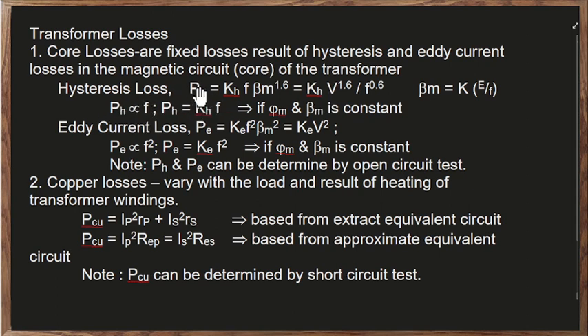P sub H stands for hysteresis power loss. We have our constant K sub H, frequency times the flux, the flux raised to the power of 1.6, no? If the given is voltage, then you have V to the 1.6 over the frequency to the 0.6. Okay, then your eddy current loss, P sub E, so we have K sub E, the constant of proportionality, F squared, then the flux density squared, or you could use the voltage, so K sub E V squared, no?